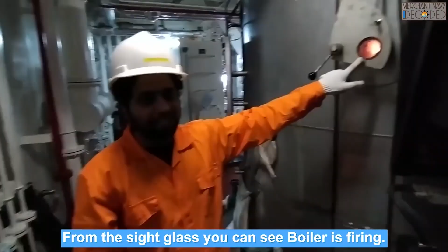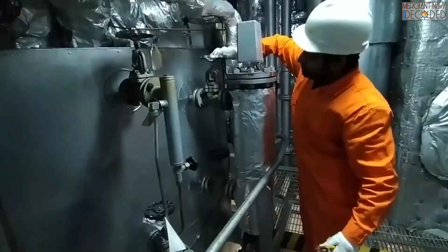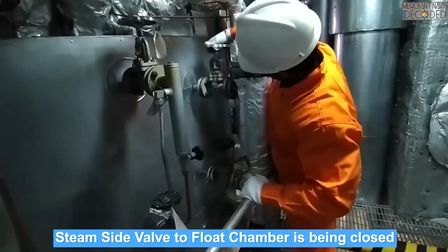Hey guys, so the boiler is firing, you can see over here. Right? Now let's go on top and try out the boiler low water level trip, which is independent of any automated system. This is what I was talking about. First I shut the steam side. Then I shut the water side.